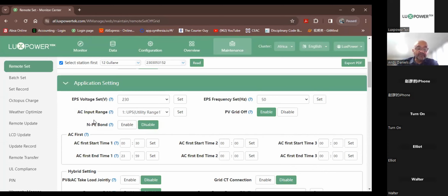This is simply a feature that has been added for something that is coming up in the future in the 6 kilowatt SNA. The current version of the 5 kilowatt SNAs that we have do not have a bonding relay built in. You still have to do your bonding manually, and it is a SANS requirement that you do the bonding. How will you know?